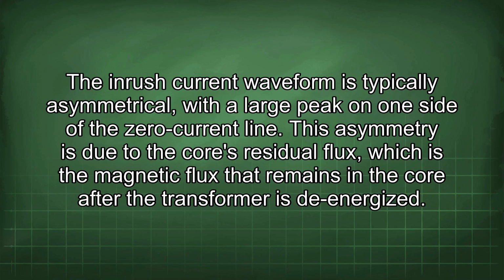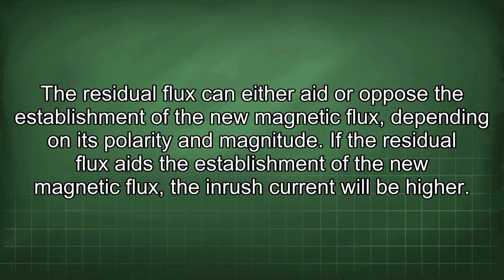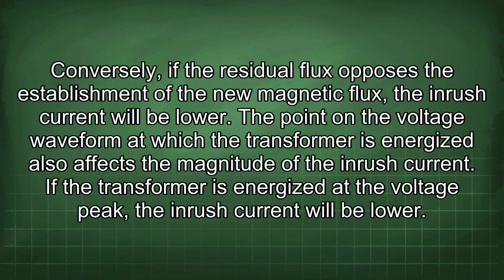This asymmetry is due to the core's residual flux, which is the magnetic flux that remains in the core after the transformer is de-energized. The residual flux can either aid or oppose the establishment of the new magnetic flux, depending on its polarity and magnitude. If the residual flux aids the establishment of the new magnetic flux, the inrush current will be higher. Conversely, if the residual flux opposes the establishment of the new magnetic flux, the inrush current will be lower.